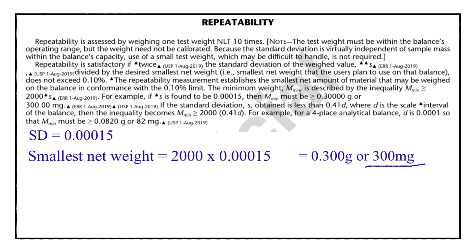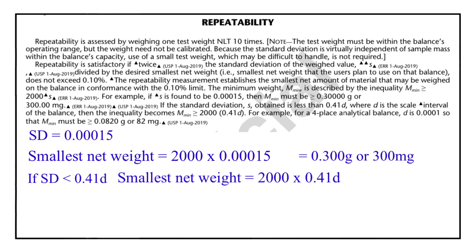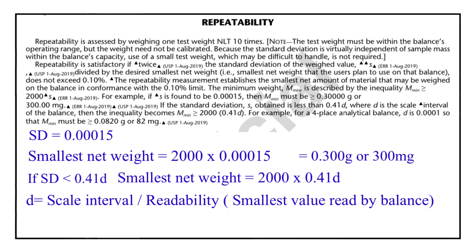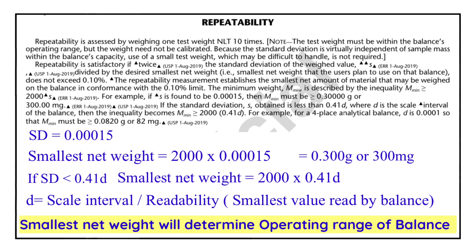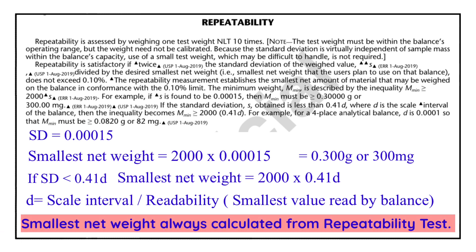We should always remember one important point: if in case the standard deviation is less than 0.41d, then to calculate the smallest net weight the formula becomes: smallest net weight = 2000 × 0.41d. Here, d is called the scale interval or the readability — it means the smallest value that is indicated or displayed by the balance. The significance of smallest net weight is that it determines the operating range of your balance. If the smallest net weight is 300 milligram, you cannot take any weight below 300 milligram. Smallest net weight is always calculated from the repeatability test.